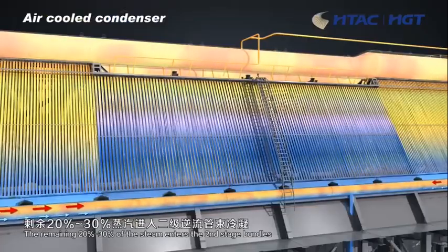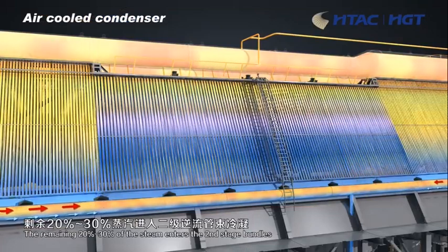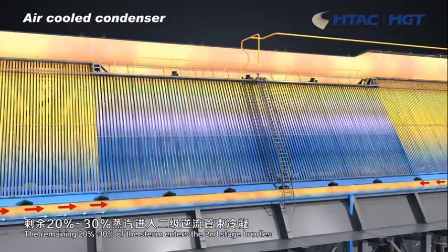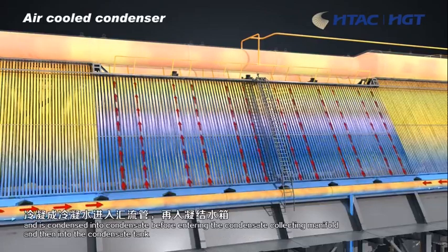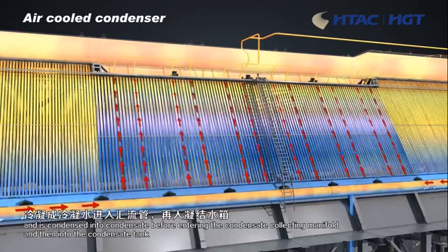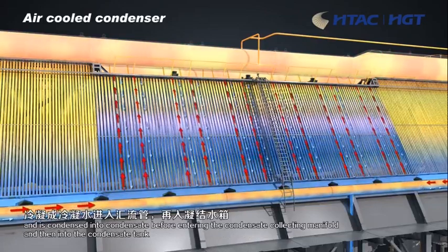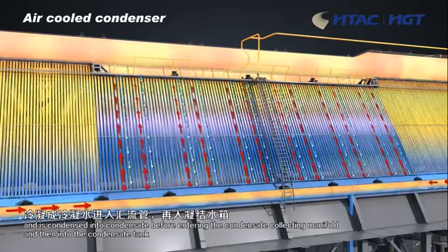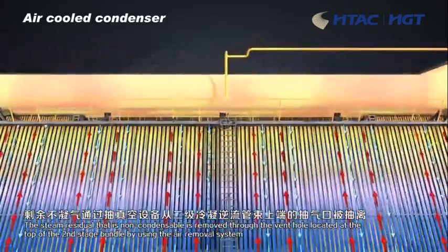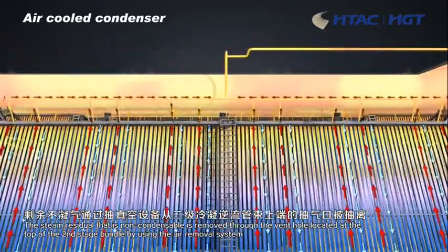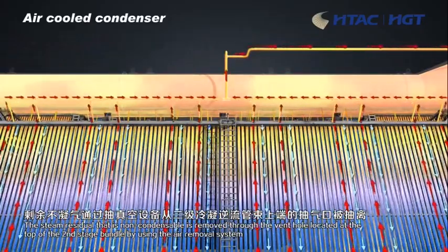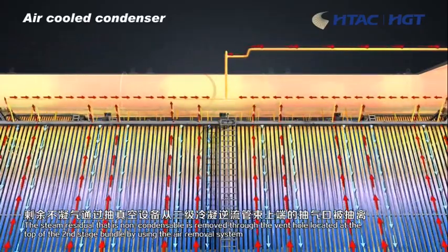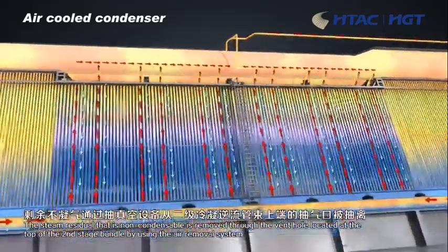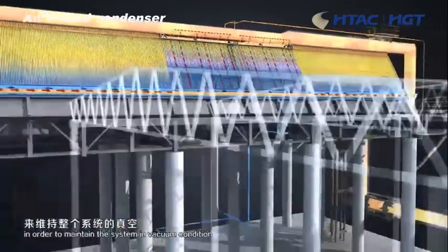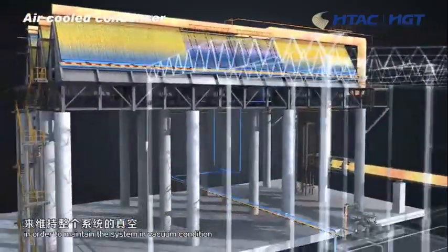The remaining 20% to 30% of the steam enters the second stage bundles and is condensed into condensate before entering the condensate collecting manifold and then into the condensate tank. The steam residual that is non-condensable is removed through the vent hole located at the top of the second stage bundle by using the air removal system in order to maintain the system in vacuum condition.